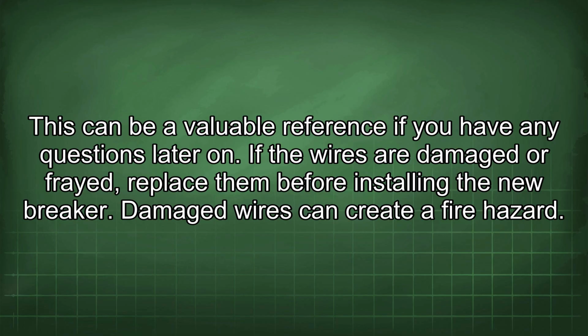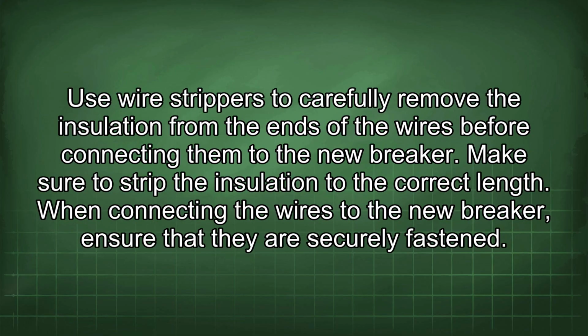If the wires are damaged or frayed, replace them before installing the new breaker. Damaged wires can create a fire hazard. Use wire strippers to carefully remove the insulation from the ends of the wires before connecting them to the new breaker. Make sure to strip the insulation to the correct length.